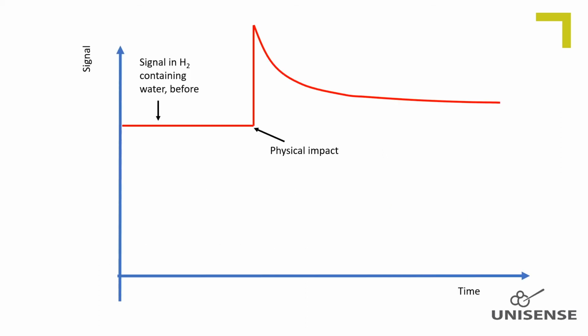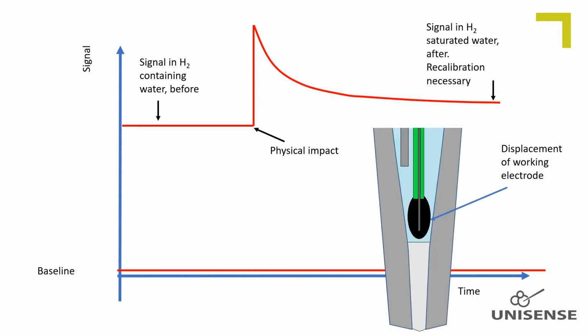Physical impact to the sensor can, besides destroying the sensor, change the sensitivity and thereby the calibration curve of a hydrogen sensor. The working electrode connects to the amperemeter via a thin, flexible, glass-covered platinum wire. Physical impact, which shocks the internal components, can induce a displacement of the working electrode position relative to the membrane, thereby changing the sensitivity. Typically, such impact will induce a sudden signal peak, followed by a stabilization time. But the sensitivity might not return to the original sensitivity caused by a displacement of the working electrode position.